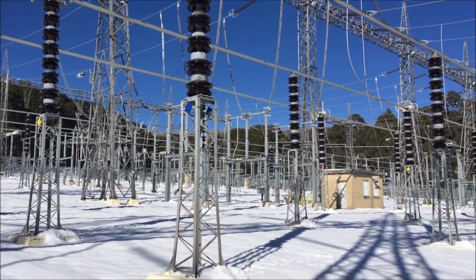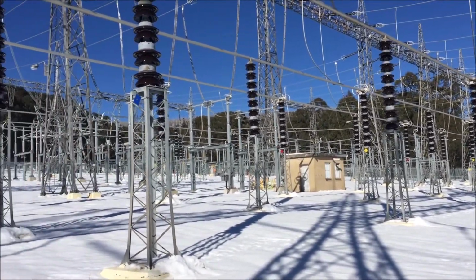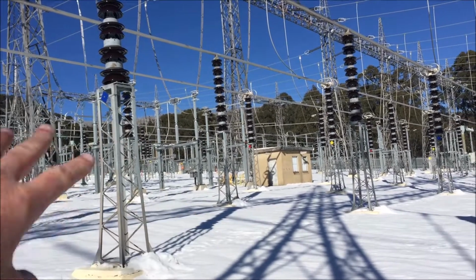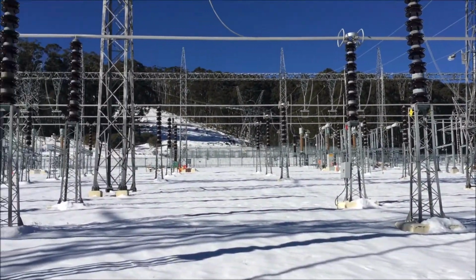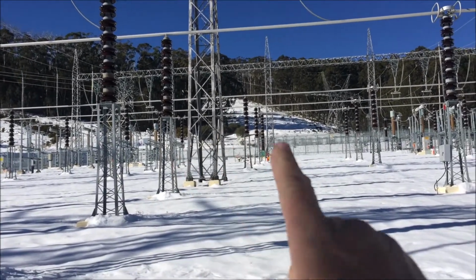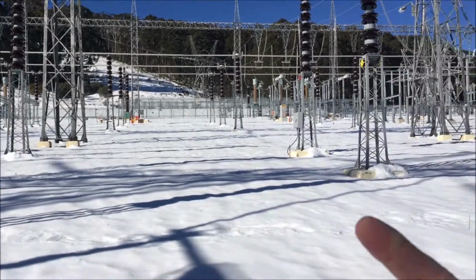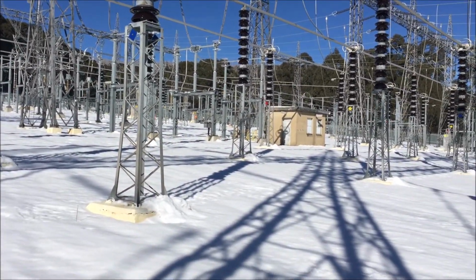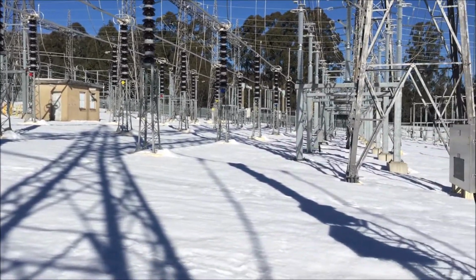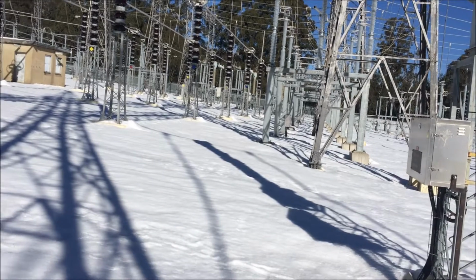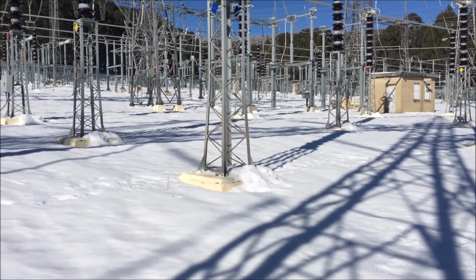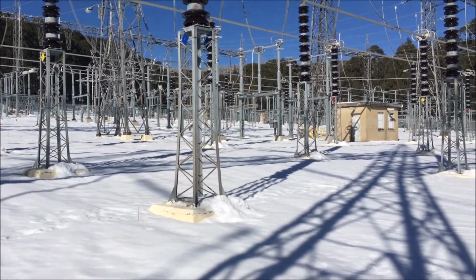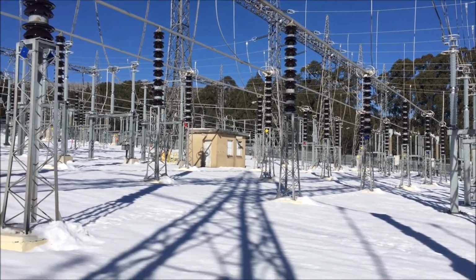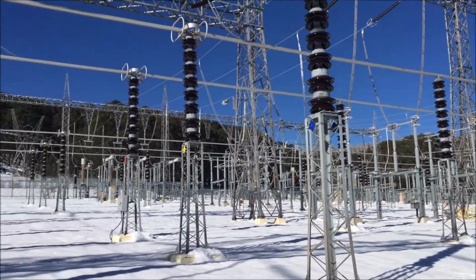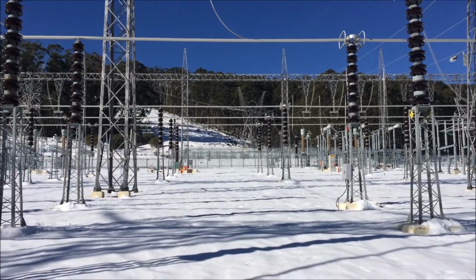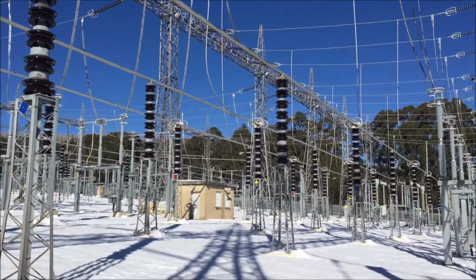They've changed it now to what they call a low impedance scheme, where instead of all the CT contributions coming into a box, which is probably gone, they all go into the relays inside, and there's also indications on each of the breakers and the isolators, so the relays inside know which line's connected where, and it all does it numerically. It says, okay, that Canberra line, it's now on the reserve bus, and that's okay, so we'll add its contribution to anything else on the reserve bus, so it all works. It's a pretty complicated system, but it's pretty good. It took a long time to make and a long time to test, but it works pretty well.